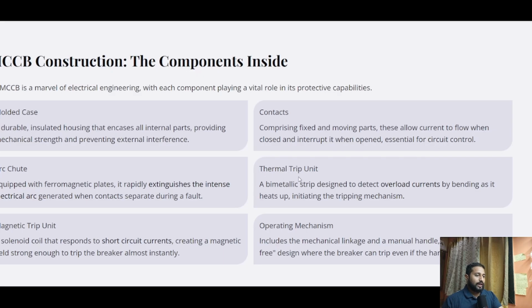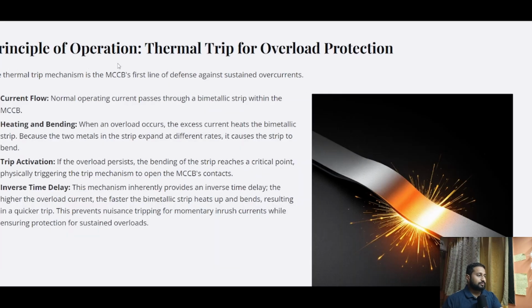These allow current to flow when closed and interrupt it when opened, essential for circuit control. Then it also has a thermal trip unit. It's a bimetallic strip designed to detect overload currents by bending as it heats up, initiating the tripping mechanism. Then the operating mechanism includes mechanical linkage and a manual handle, ensuring trip-free design where the breaker can trip even if the handle is held on. The principle of operation, it has thermal trip for overload protection.